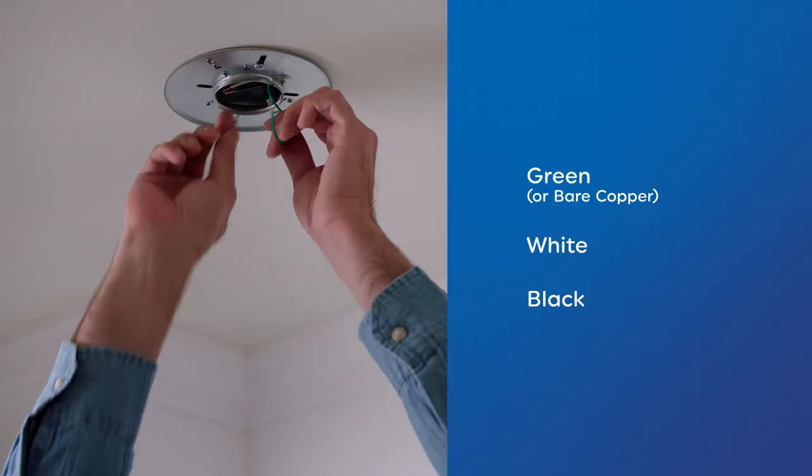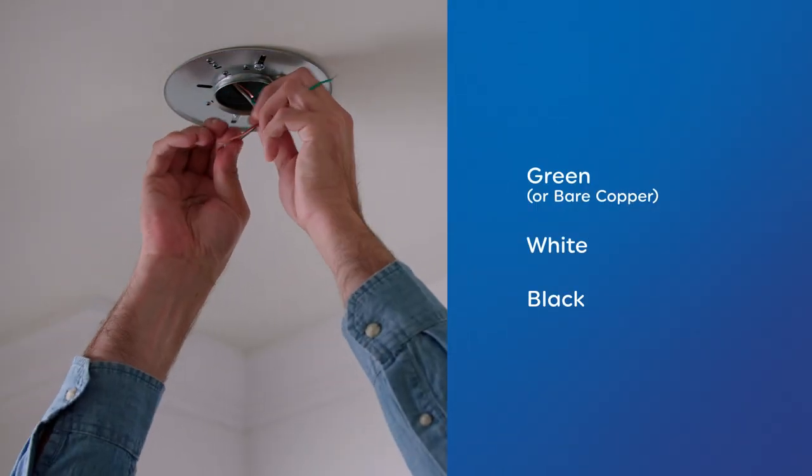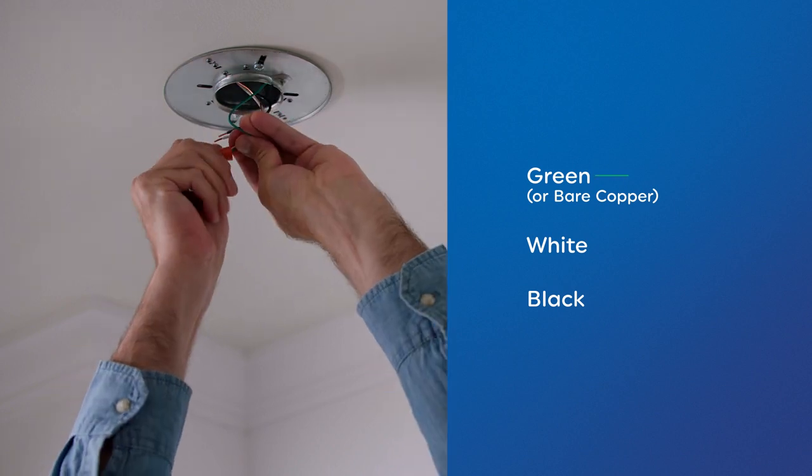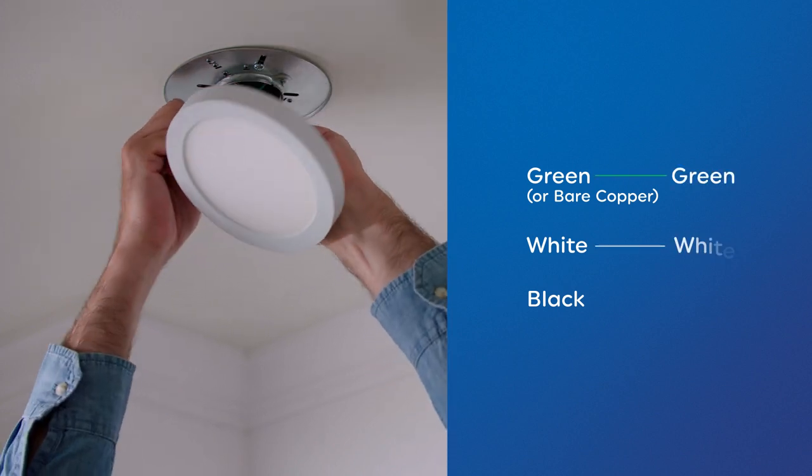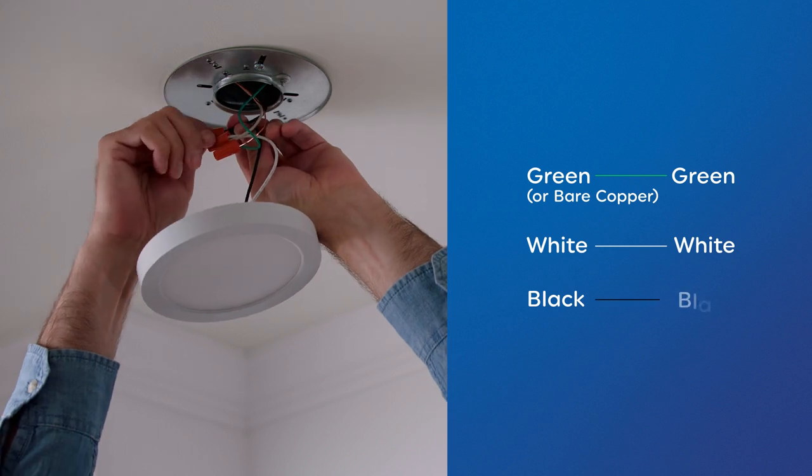Now connect the fixture wires to the corresponding wires in the junction box and secure with wire nuts. Cap the green and bare copper wires. Connect the neutral white wire to white, and the black line wire to black.